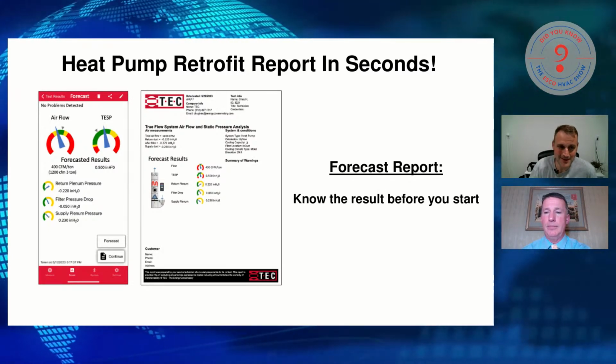Yeah. Dude, I'm guilty of that. I have done it. Hand raised, right? I have had to go in homes and replace supply ductwork because I missed the mark and my external static pressure was too high. Absolutely.